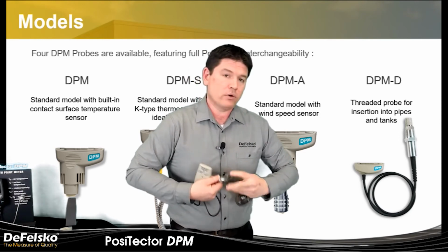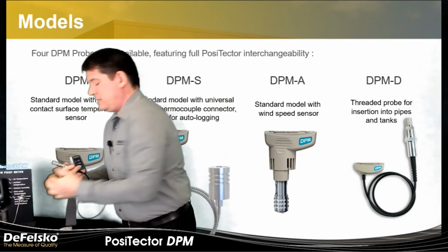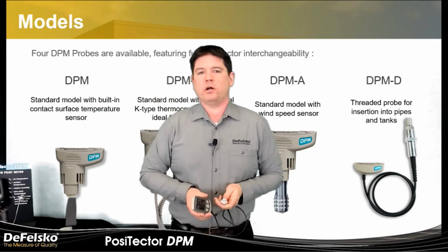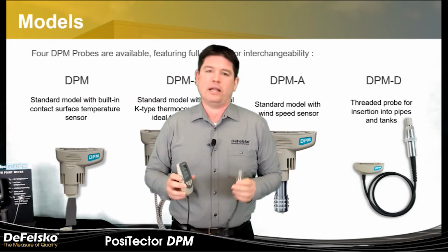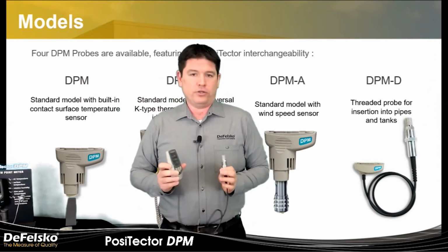This does not record surface temperature. Obviously, the sintered metal end is in place of where the surface temperature sensor was, but our general experience with talking to our pipeline customers was that they did not require that particular sensor. They were more interested in air and dew point.